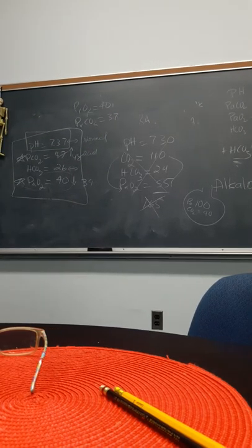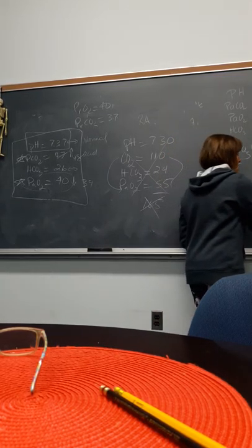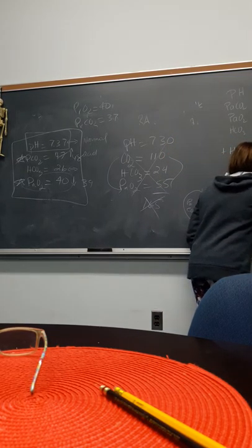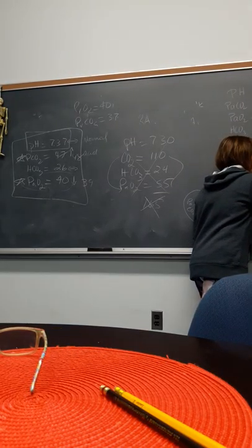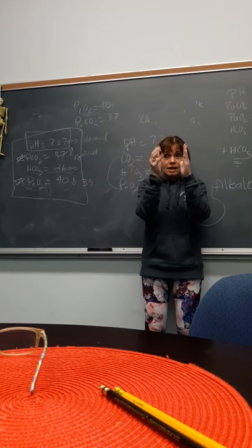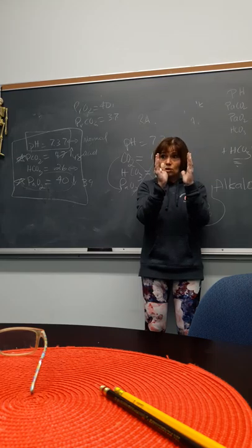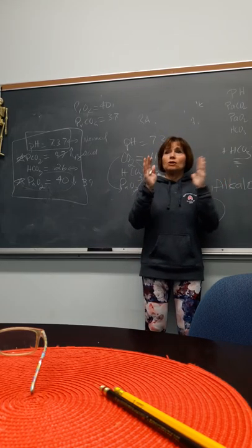Martha, the machine that we did the QC on yesterday, the range is different, like for CO2. Is it normal? Because we know what's going to happen when you run QC: there are going to be three vials. So we run three different vials a day, every 8 hours, they run one. One's going to be acid, one's going to be normal, one's going to be alkalotic. Each vial has a specific range for pH, CO2, and O2. So whichever one you're using, you're going to do that.